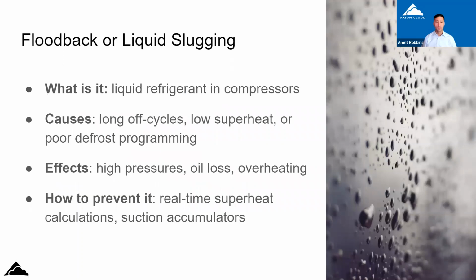So our first topic area is floodback or liquid slugging. The way I like to talk about this is essentially compressors are made to compress gas. They're not made to compress liquid. In fact, liquid is incompressible, if you remember your high school physics. And anyone in the refrigeration industry knows that if liquid is entering the compressor, that's really, really bad. Trying to compress liquid can result in pressures as high as 3,000 PSI, which is not good for anyone involved, any stakeholder.